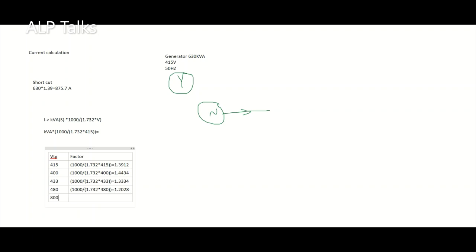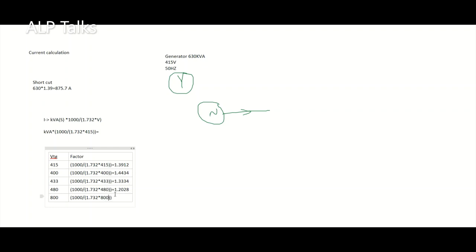Let's calculate for 800 volts, generally used in inverter applications, the factor is 0.7217. Like this, you can simply multiply the kVA with the factor and you will get amperes directly.